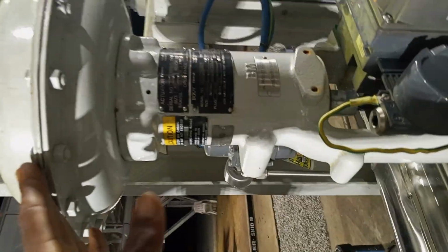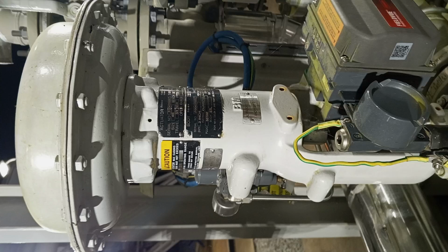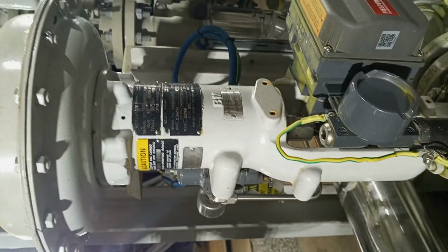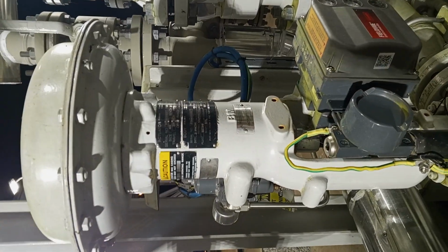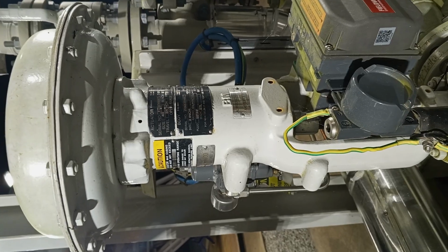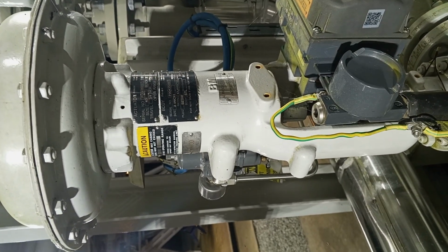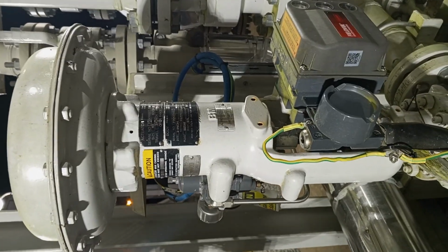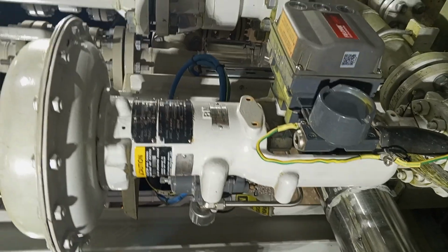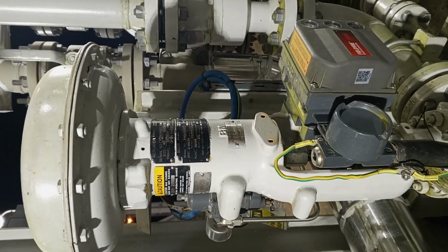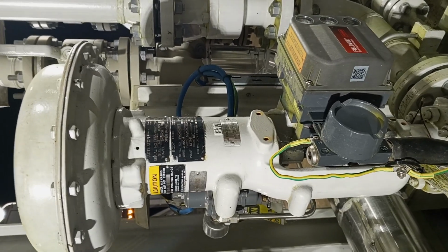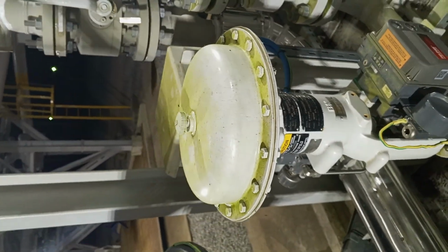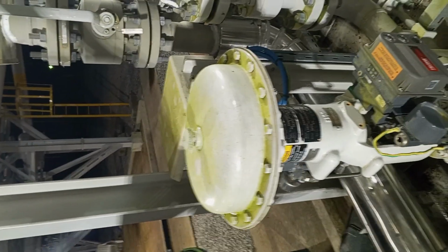So this pressure control valve, these valves' names are given based on the purpose in the process line. Its purpose is to regulate pressure in the system using signals from the pressure transmitter. What this means is that the pressure transmitter will measure the pressure on the line and send the information to the controller, and the controller in return will take action on how the valve should operate and at what level the valve should open or close.